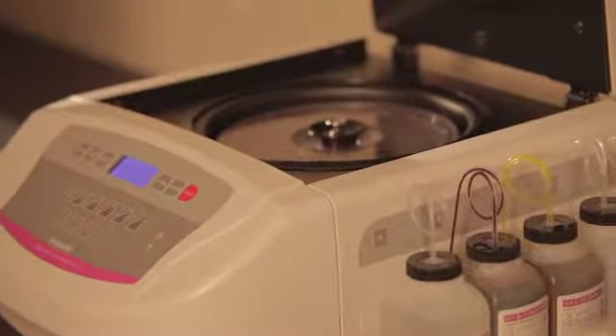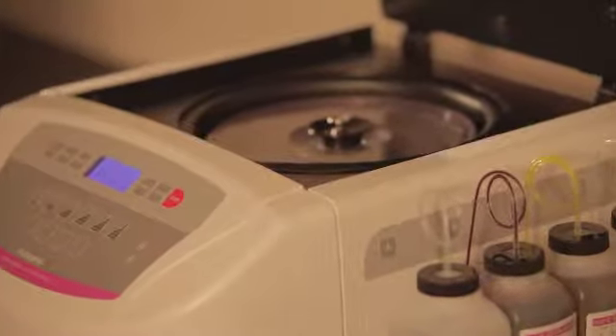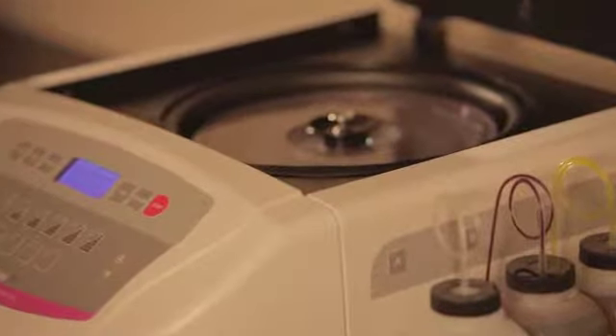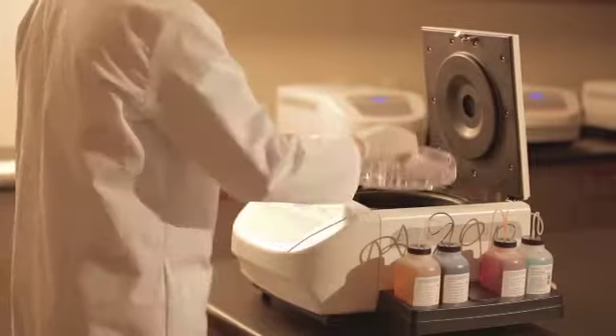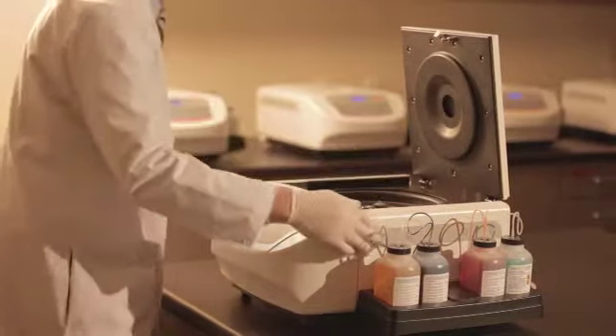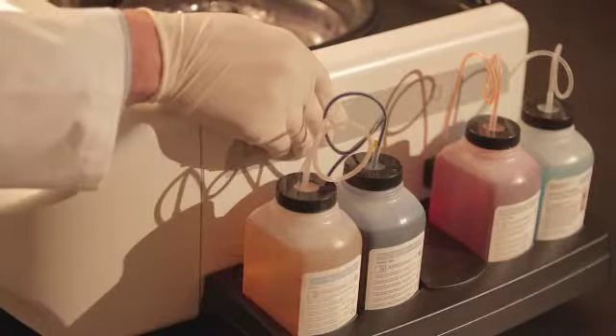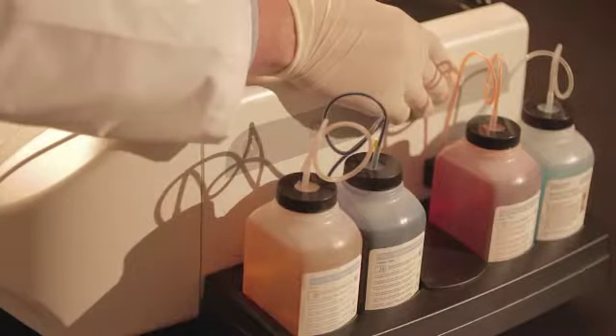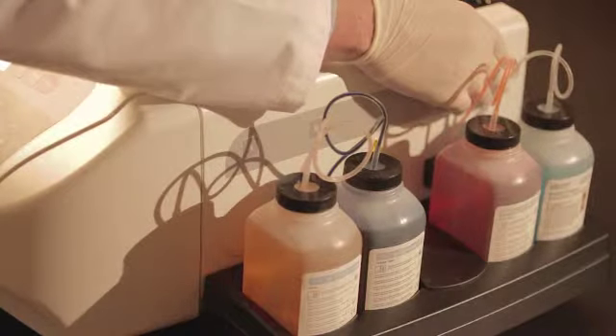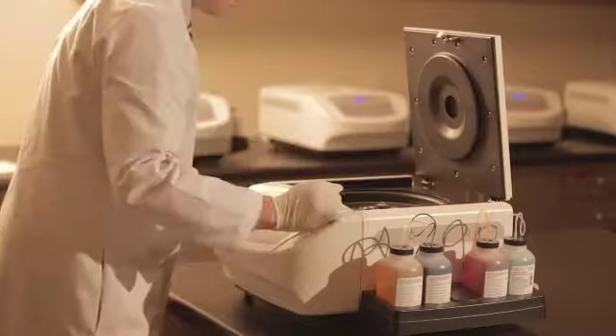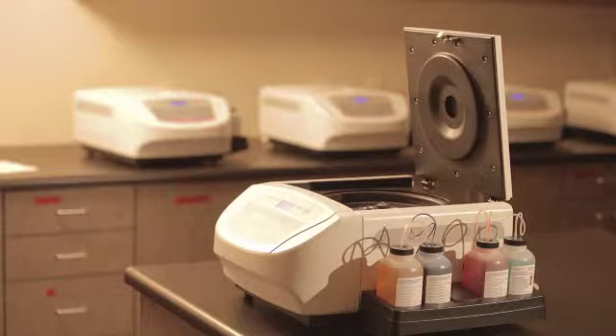It is now time to prime the reagents through the internal plumbing of pumps and valves of the stainer. Place an empty carousel inside of the stainer. On the right side of the stainer above the dip tubes, there are prime buttons for each line. Press one prime button at a time and make sure some stain is sprayed out of each respective nozzle. If stain does not come out of each nozzle, the priming tool provided in the nozzle maintenance kit should be used. This is used by removing the nozzle, screwing in the adapter, pulling the syringe plunger back to create a vacuum, and pressing a prime button.